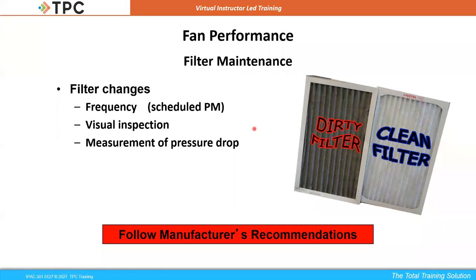What we're looking at is checking the pressure difference between one side of the filter and the other side of the filter. I'm going to put a brand new filter in there, and I'm going to measure how much drop in pressure I have across there. As the pressure increases, that means the dirt is getting blocked up in the filter, and I've got too much dirt built up in there, so I need to pull the filter out and change that filter.